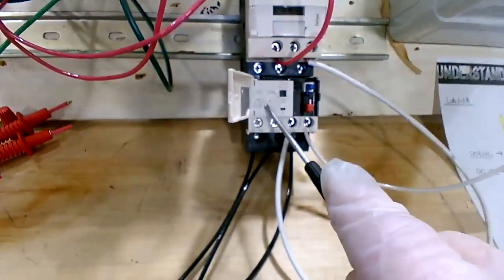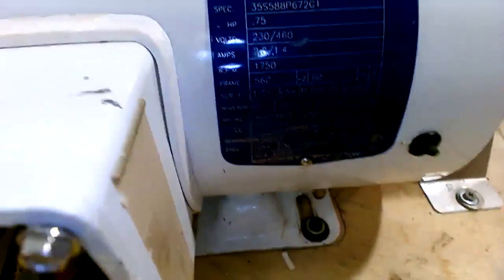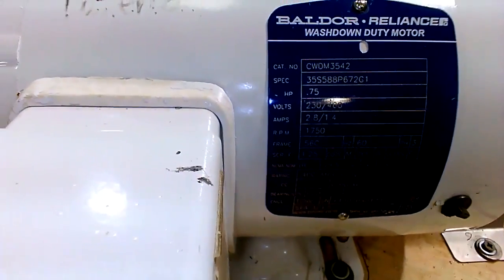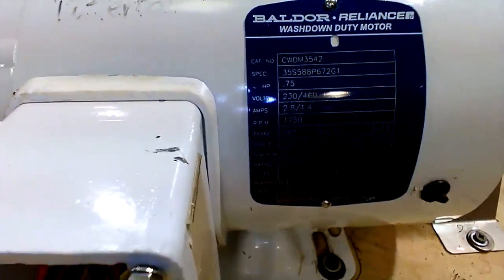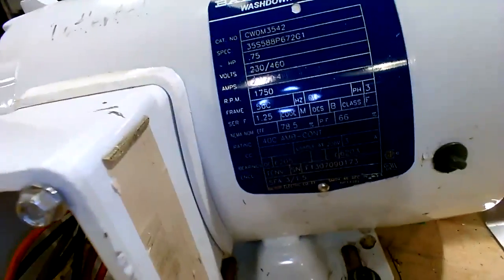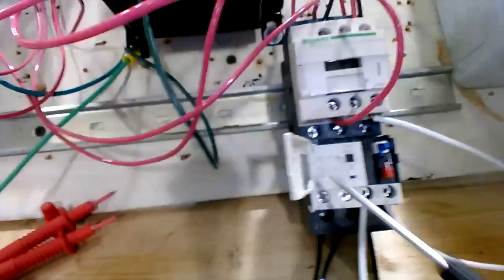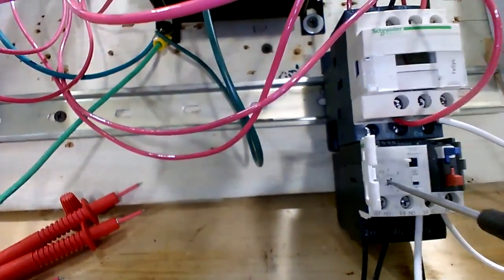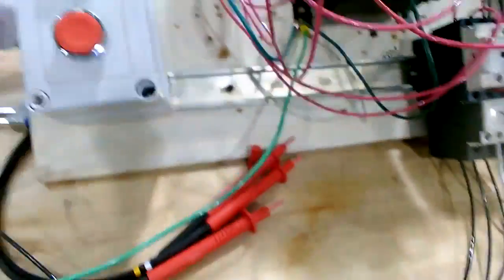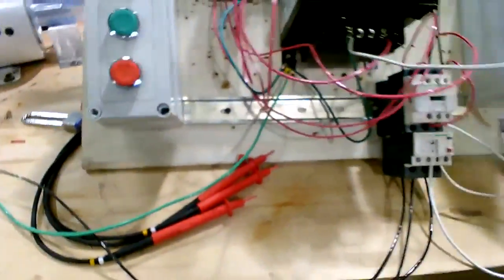The way you pick your set point for this is you go to the motor, you get that amp setting right there, that 2.8, and you multiply it by 125%, by 1.25. You boost it up, and it gives you some extra amps. So you take the 2.8 times 1.25, and you set that. We'll be covering that in the book down the road. That's the correct way to set the overload. Don't assume it's been set correctly, as it could be set way too high or way too low, when you go up to it. Okay?